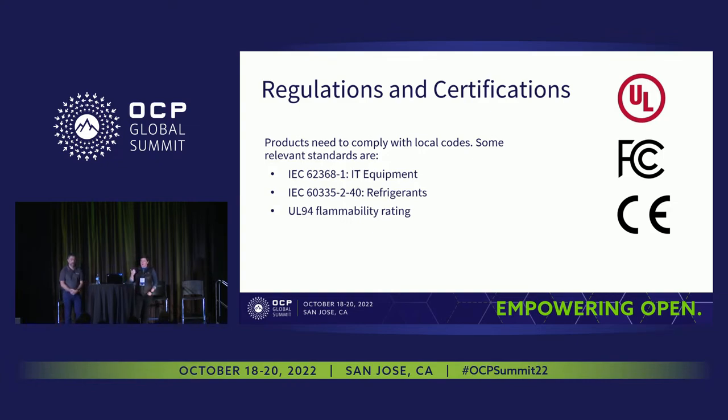And then thirdly, we mentioned trying to draw some dotted lines and knit in some other industry guidance and certainly local and regional regulations that might be of interest to these cold plate applications. A couple that jump out here are the latest revision of the IEC standard 62368 around IT equipment. And that now has a subset specific for liquid cooling components. In there, you're going to find some guidance around safety magnitudes for things like operating and burst pressures.